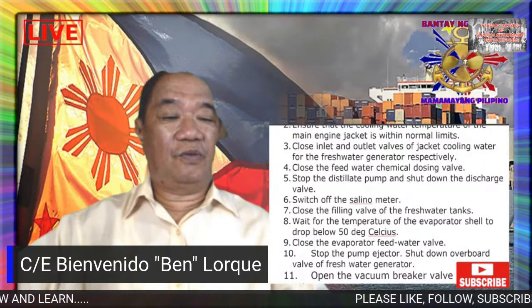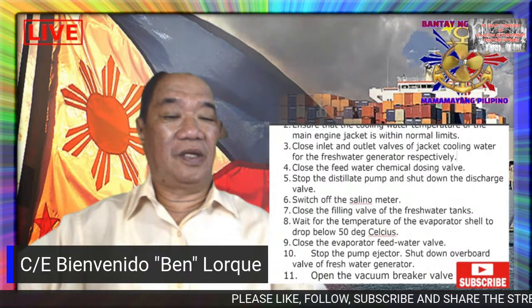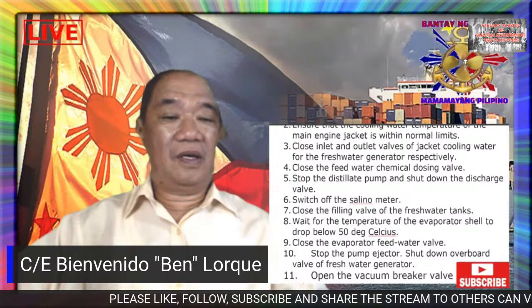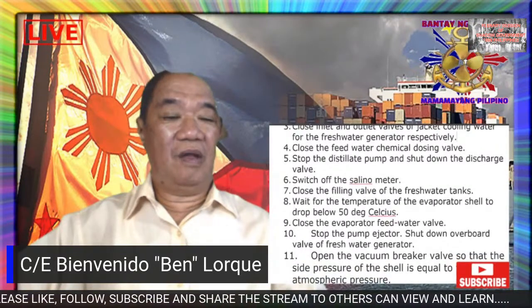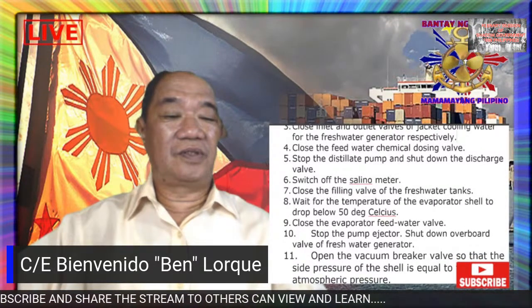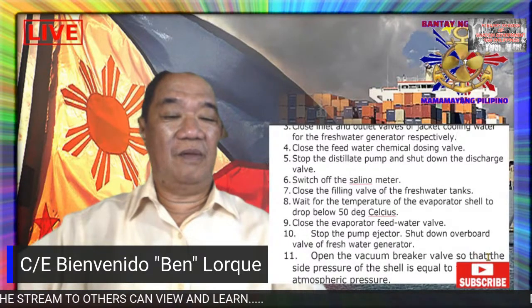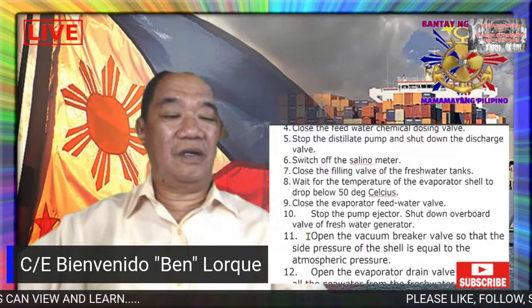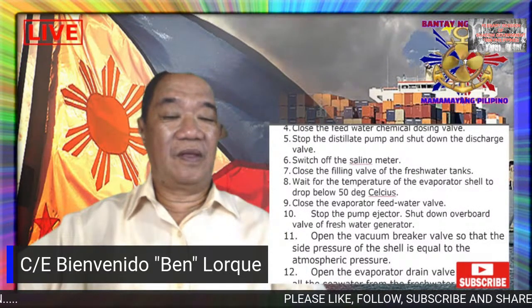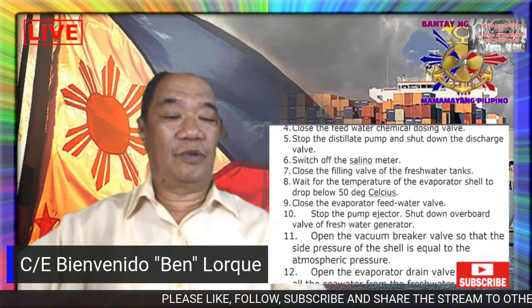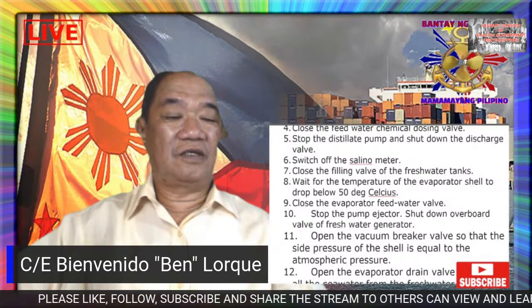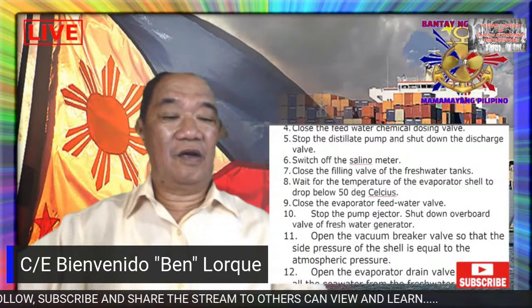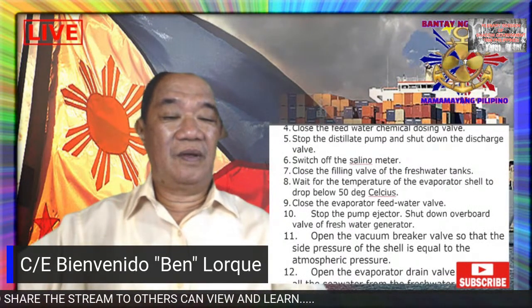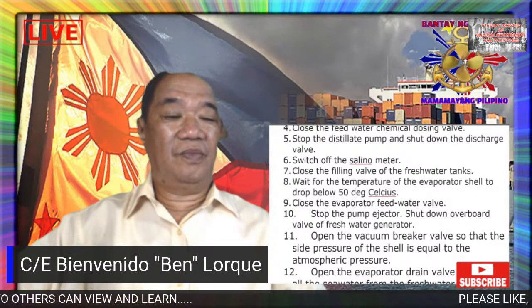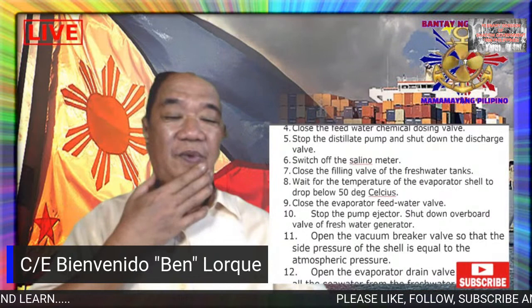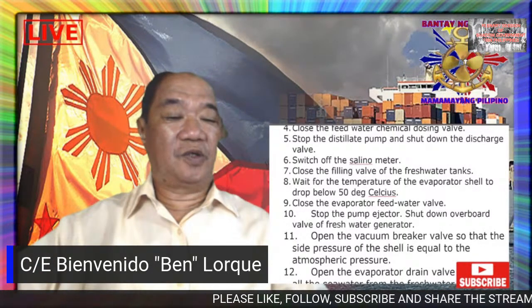Wait for the temperature of the evaporator shell to drop below 50 degrees centigrade and close the evaporator feed water valve. Stop the ejector, shut down the overboard valve and the suction valve, then open the vacuum breaker valve so that the pressure inside the shell is equal to the atmospheric pressure. By doing that, you are avoiding corrosion inside the shell. Then open the evaporator drain valve to drain all salt water from the freshwater generator.